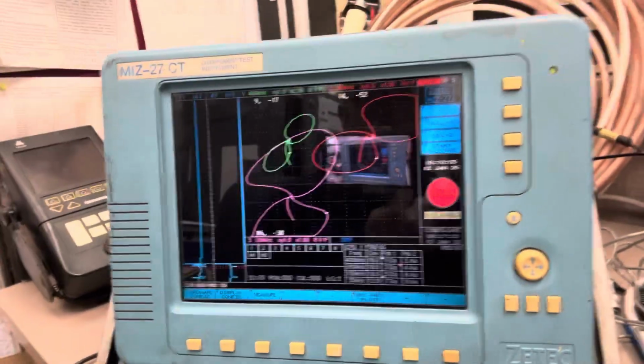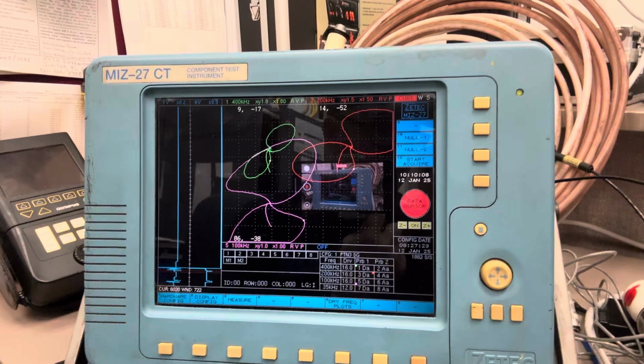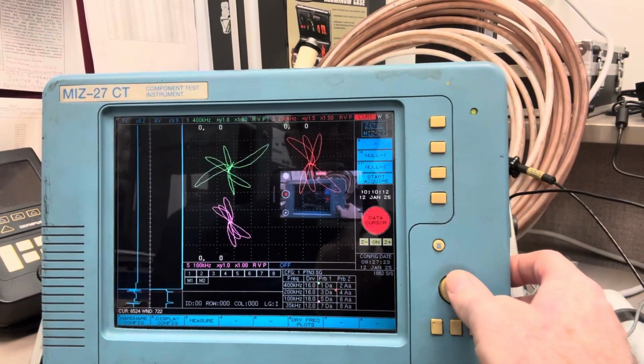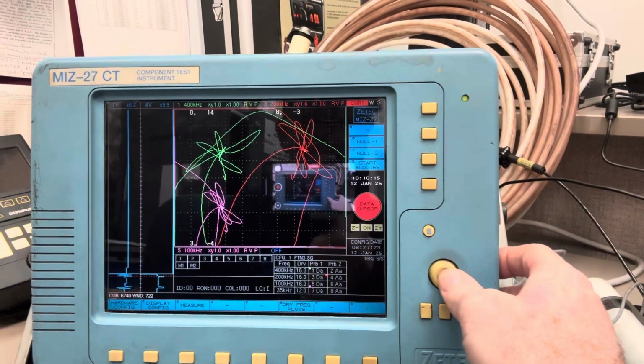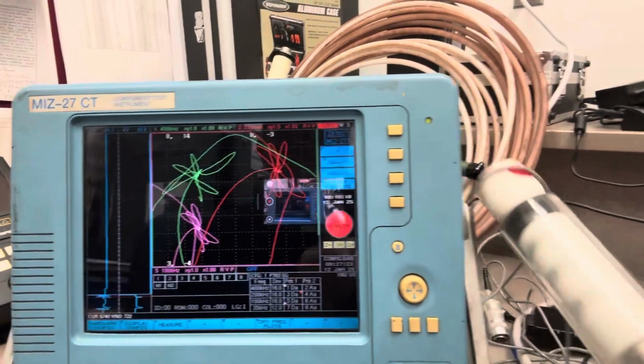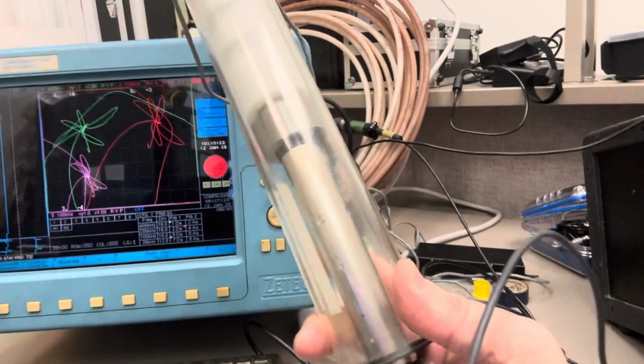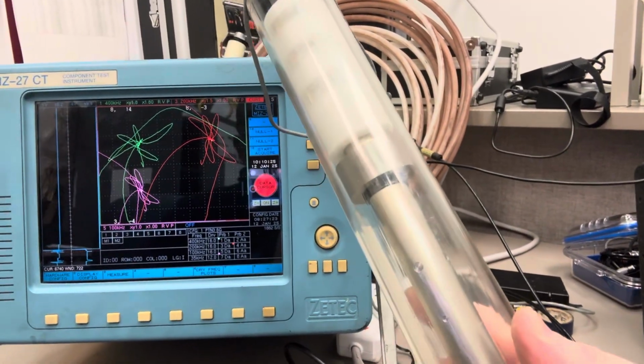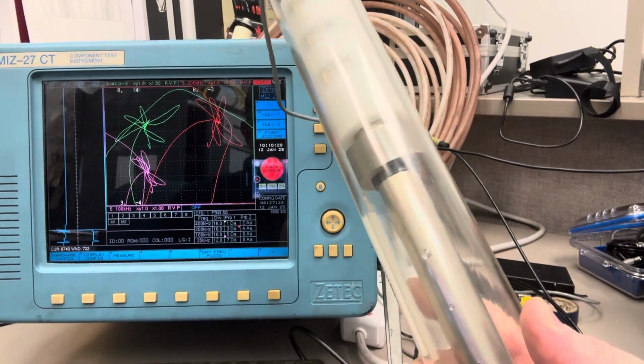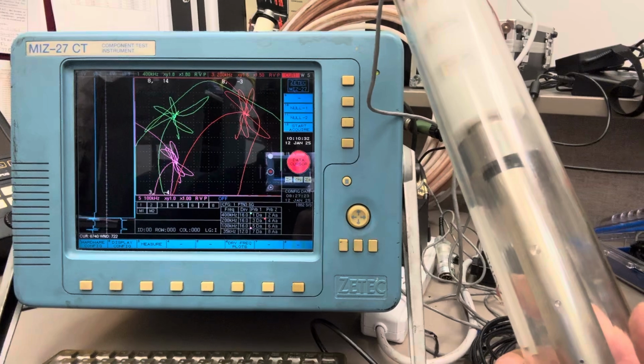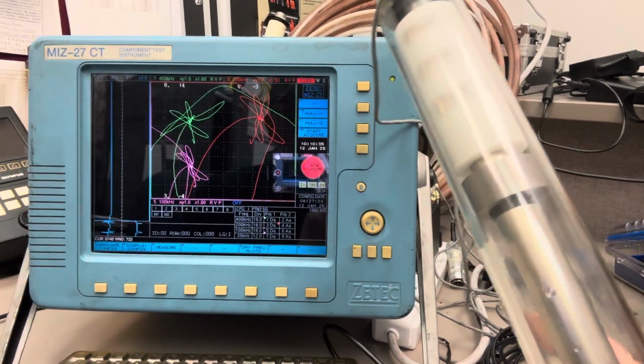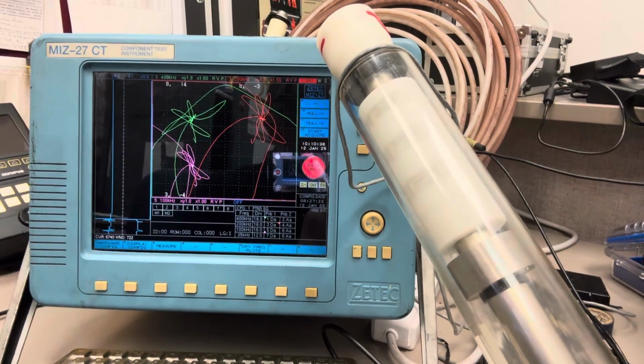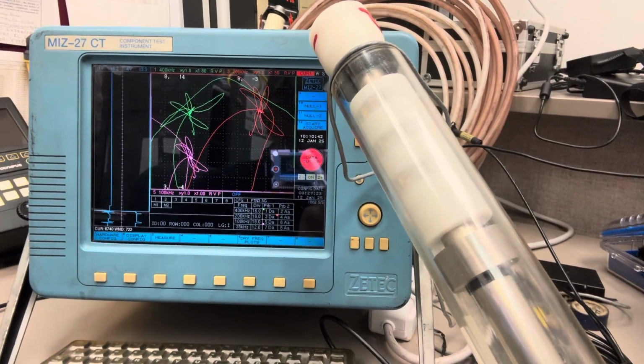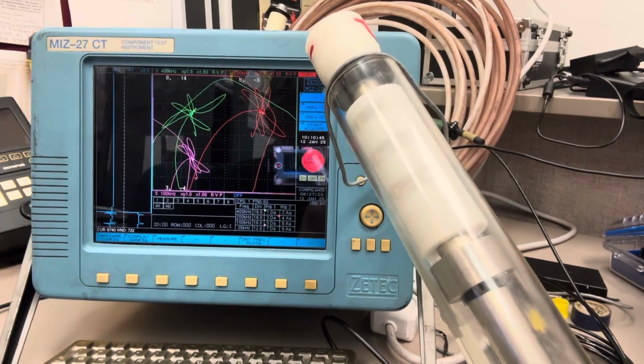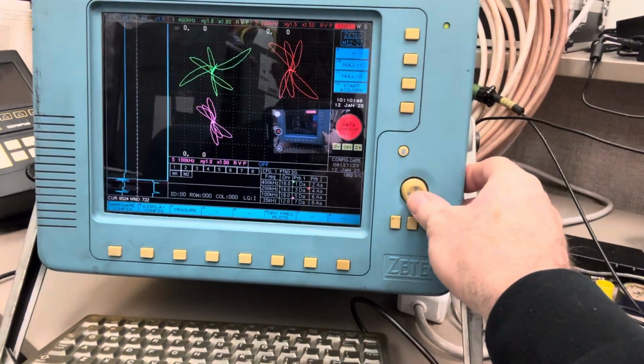What does that look like? This is an older test instrument, but it shows what eddy current data looks like. These signals on the screen are actually flaw signals from a calibration standard, which is what you're looking at here. This calibration standard has a bunch of known flaws or defects, ranging from flat bottom holes maybe 20% deep, to a through-wall hole. This white area toward the top has some tube support rings with mechanical wear fretted into the tubing. So we calibrate our test instrument to recognize what those signals look like.